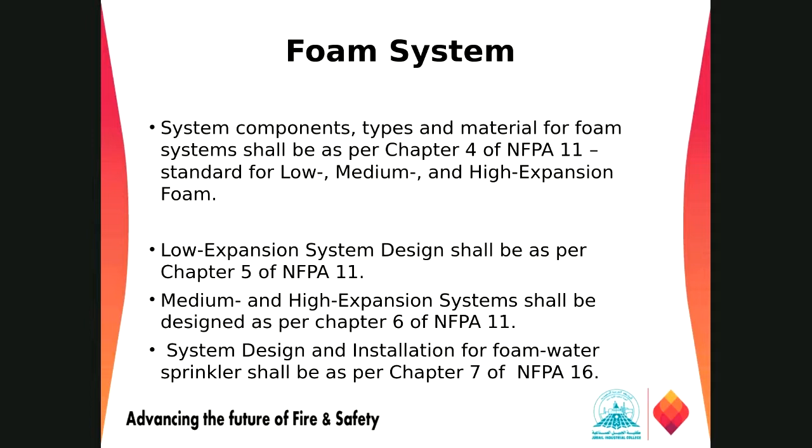So for the system components, look for them as per NFPA 11 chapter 4 for low, medium and high expansion foam. And the low expansion system shall be designed as per chapter 5 of NFPA 11. Remember we discussed the low expansion system for storage tanks, the dike protection and all those areas. Medium and high expansion foam shall be as per chapter 6 of NFPA 11. While for the sprinkler system, foam water sprinkler system is totally different from NFPA 11. So it shall be designed as per chapter 7 of NFPA 16.